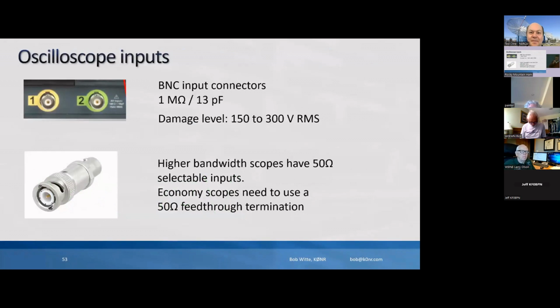Let's see, scope inputs. We'll talk about VNAs and spectrum analyzers later. Those are usually pretty sensitive inputs, as in you can blow them up if you aren't careful. Scopes are pretty rugged. Damage level is usually spec'd at 150 to 300 volts RMS, somewhere up there. It's a 1 megohm input, so it's inherently high impedance. And it does have some parallel capacitance in there that will affect the high frequency measurement, typically like 13 picofarads.